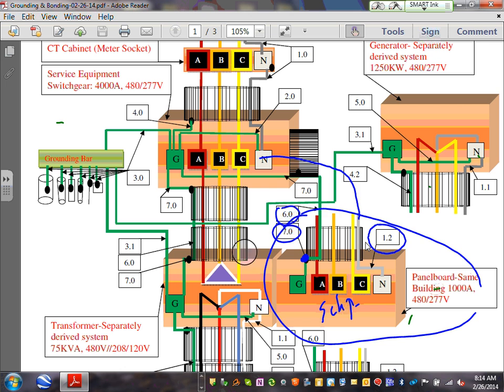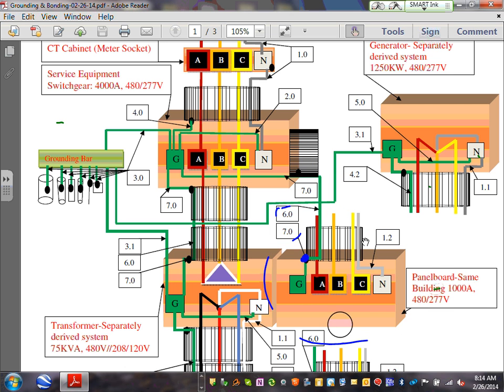So let's do grounding and bonding on a sub panel. Grounding and bonding on a sub panel. So Adam, this one here is equivalent to being done with the switchgear, the first panel. This one here is equivalent to bonding right here at this panel.